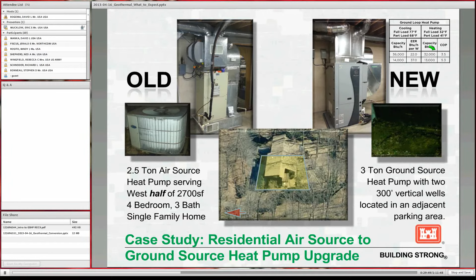What I ended up doing was replacing it with a Series 7 water furnace, which is a variable speed. At the time, and I think still is, the only variable speed compressor on the market. Most of these things are dual speed scroll compressors. And that was coupled on the outside with two 300-foot vertical wells in a little parking area next to my house. And if you can read the fine print up here, you can see the coefficient of performance, basically indicating that since you're moving heat instead of generating heat, you can actually get over a 3 or 4 to 1 ratio return on your electrical investment. So for every 1 unit of electricity you use, you can get 4 units of heat back into your house.